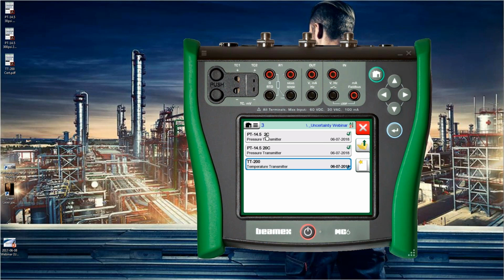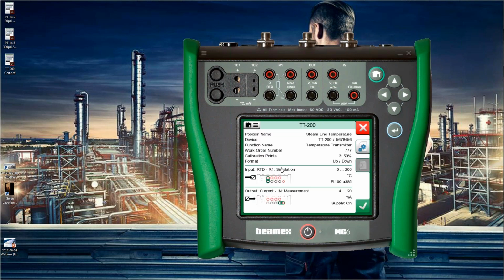So with this, what am I doing next? I'm doing this. I've got a calibrator hooked up to an RTD temperature transmitter, and I'm using the calibrator to simulate an RTD probe, and I'm also measuring the current output from it as well as providing loop power. So I've taken the numbers that Ned had given us previously, and I've got TT200.